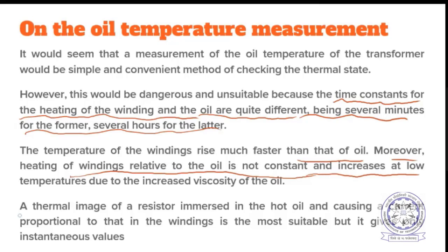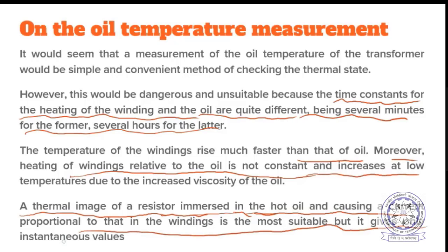A thermal image of a resistor immersed in hot oil. What can be done is that a resistor can be immersed in hot oil and a current proportional to that in the windings caused to flow through it. This is most suitable, but it gives only instantaneous values. For example, you have a resistor, and you allow a proportional current to flow through it, whatever the winding current is, and immerse that resistor in oil and find out the temperature using a thermal image or whatever it means.